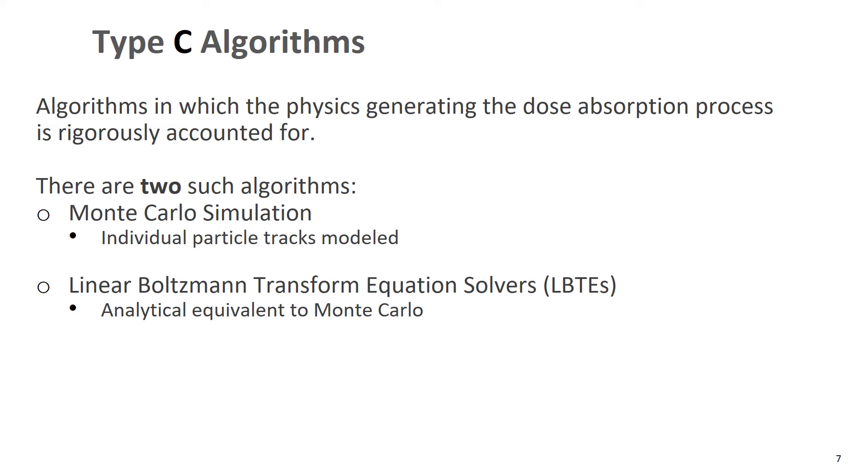So let's talk about type C algorithms. We've defined these as algorithms in which the physics generating the dose absorption process is rigorously accounted for. And really there's two such algorithms. One is Monte Carlo simulation in which the individual particle tracks are modeled. And the other, which is newer on the scene, is linear Boltzmann transform equation solvers. This is an analytical equivalent to Monte Carlo. And we'll get into a little more detail on each of these.